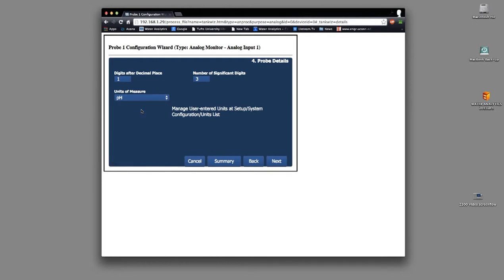No pH reading in a process is capable of accuracy better than 2 places, so I'll enter 2 for the number of digits after the decimal place. And because pH can have double-digit numbers like 10 or 14, that gives us a total number of digits of 4. So a reading might be something like 11.42, for example. Okay, we're done with that.